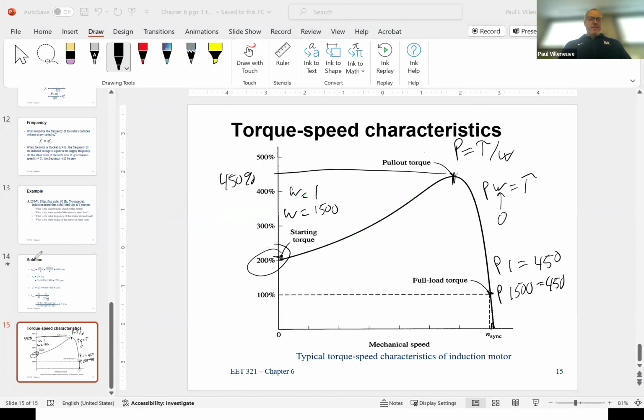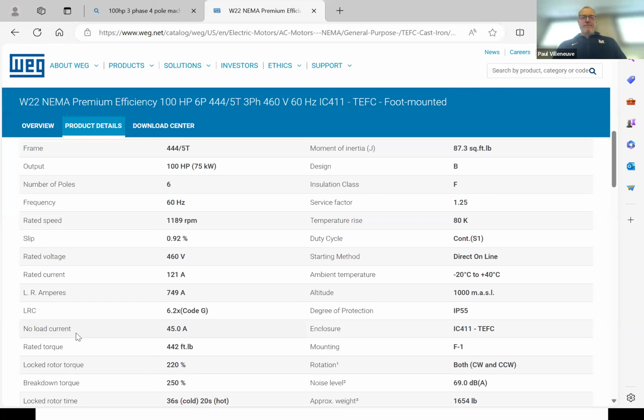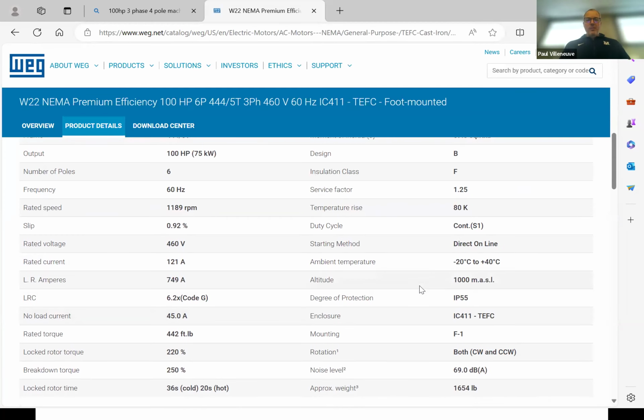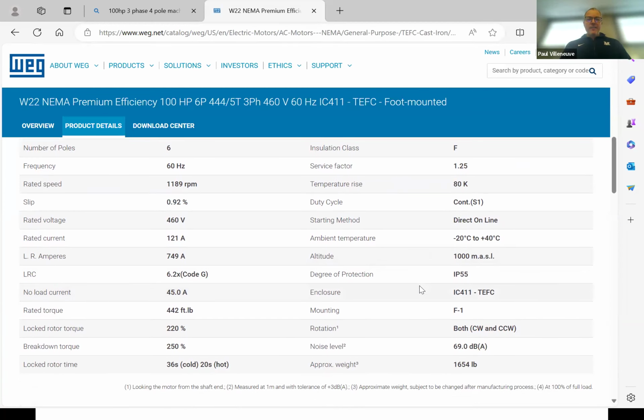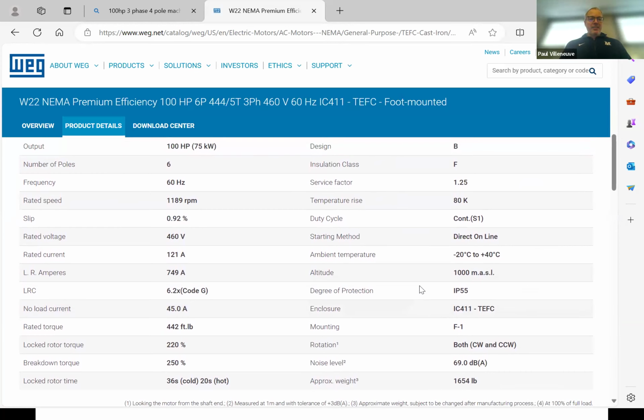So if I go back to that nameplate, this is a premium efficiency motor. So what is the full load efficiency on here? It says premium, but it doesn't actually tell you what that is.